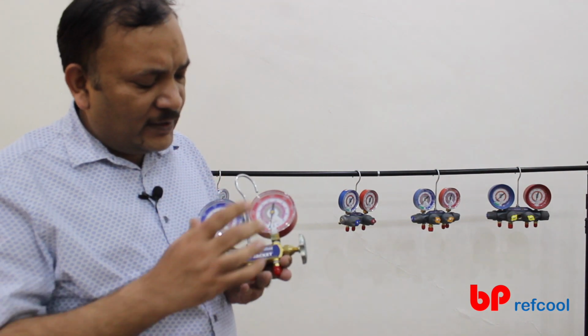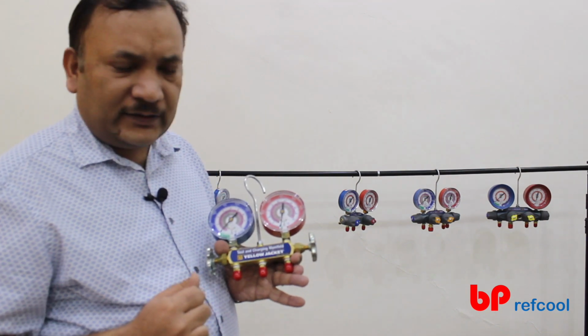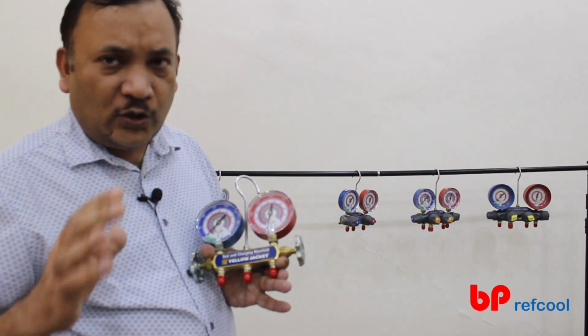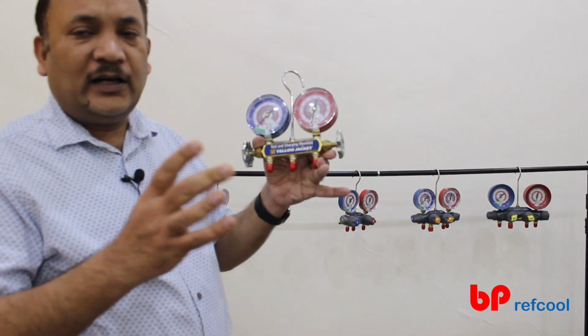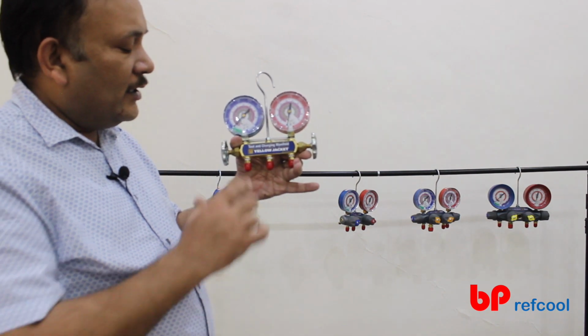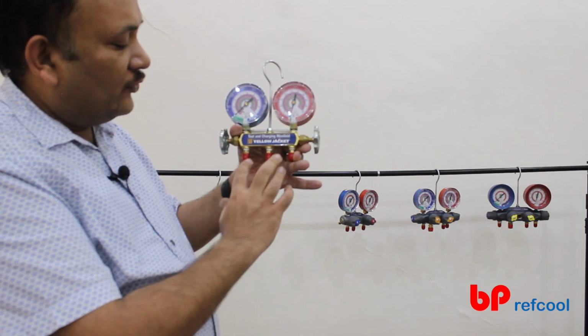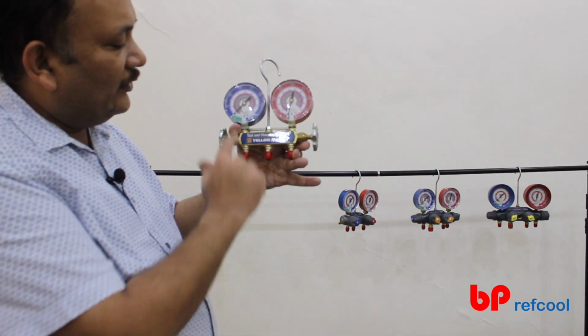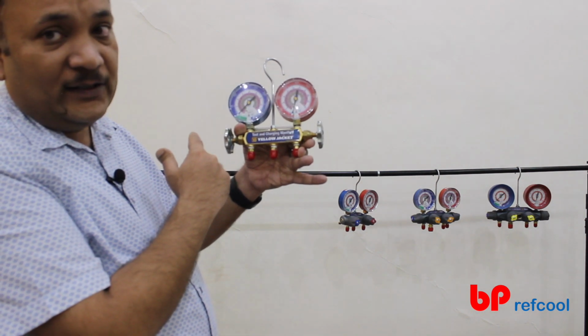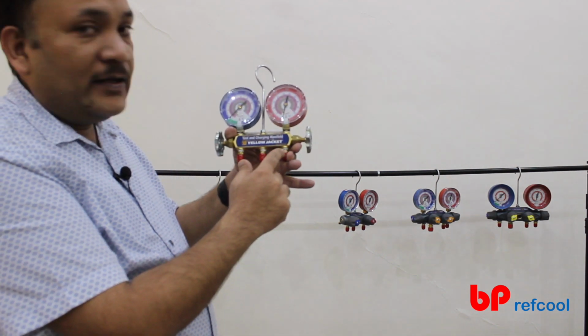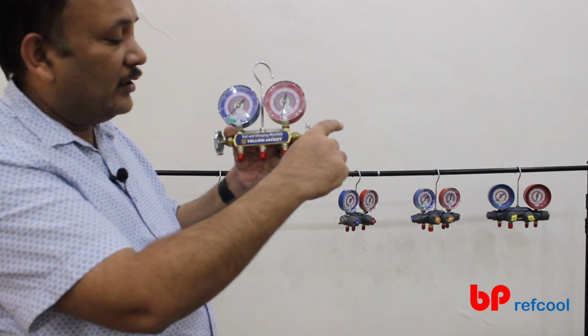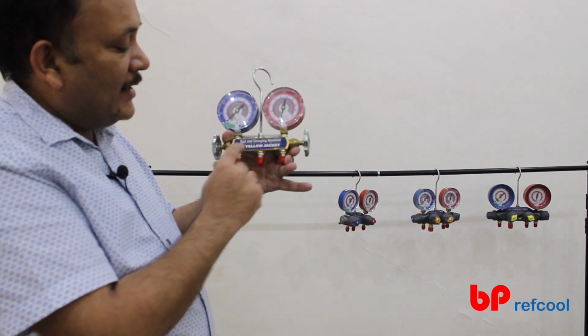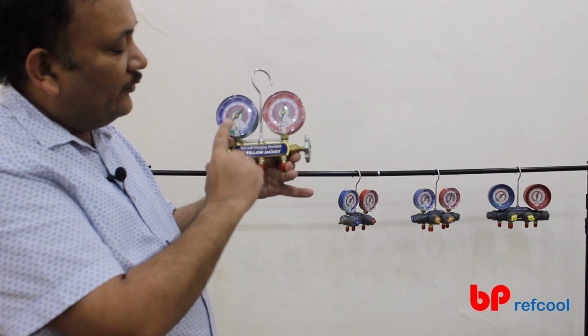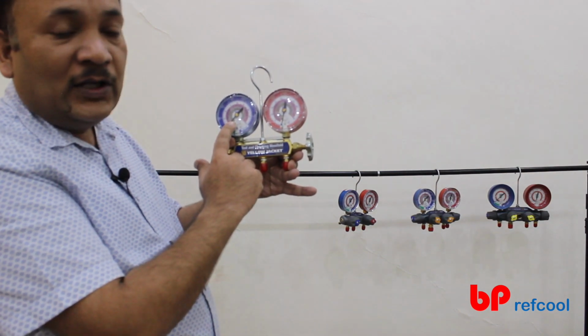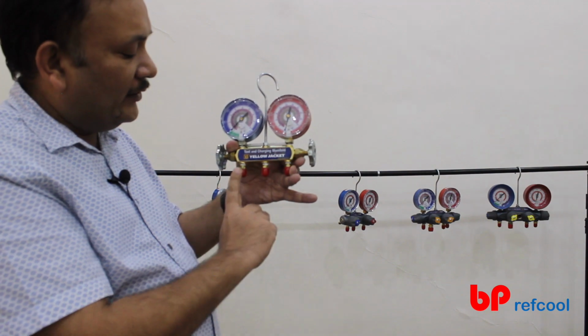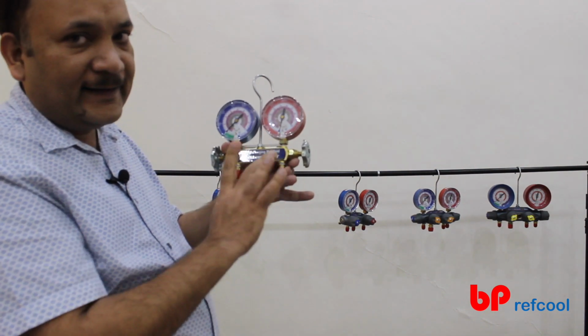So we talked about gauges, the material, and the glass. Another thing to know about these gauges, say in this two-way manifold, is these three connections. This blue one we connect to the suction side of the system. This red one we connect to the discharge side or the liquid side of the system. Whatever is connected here will be displayed directly on the gauge, so you don't need to operate any valve for this and for this. They are directly connected.